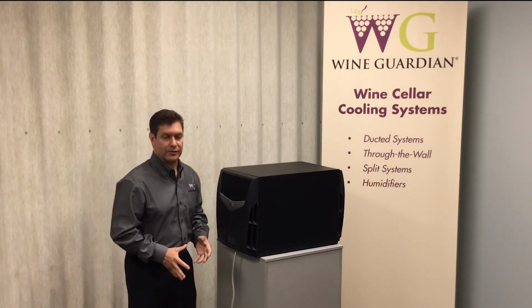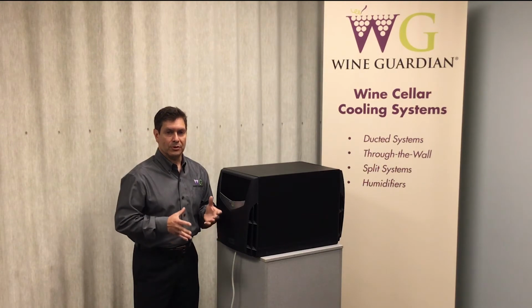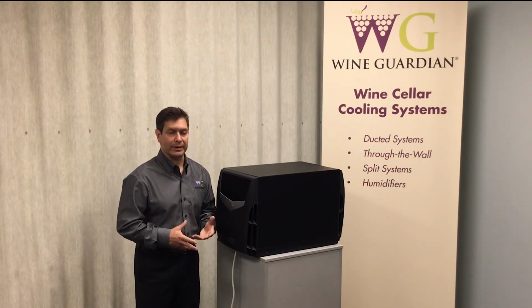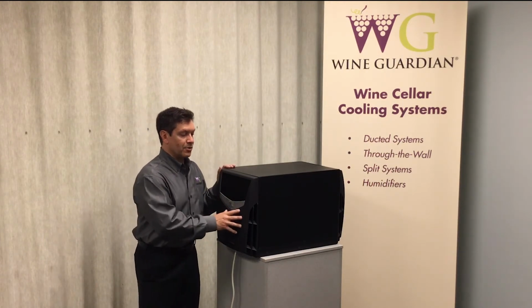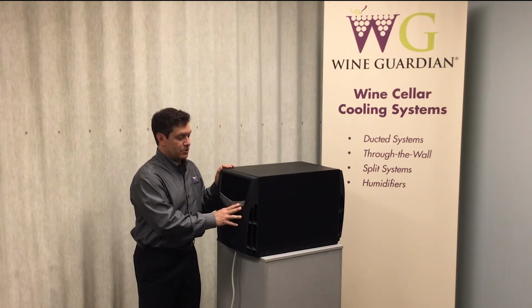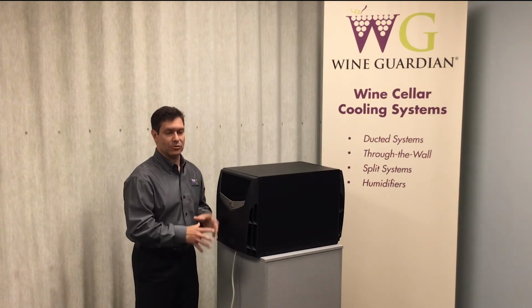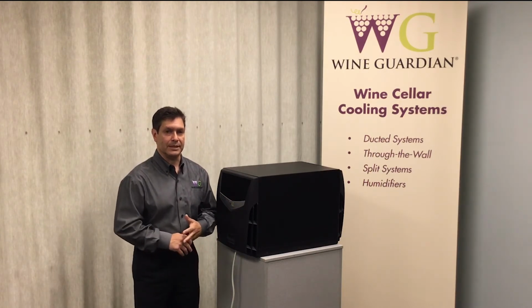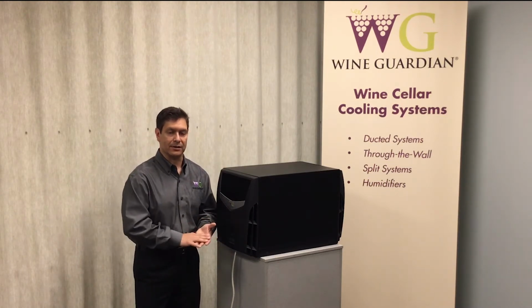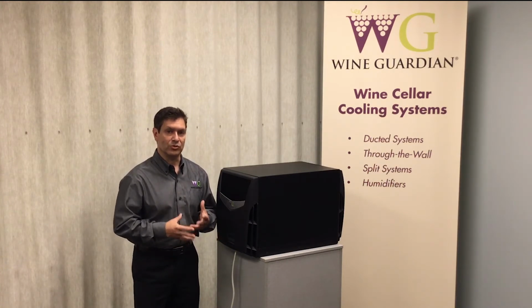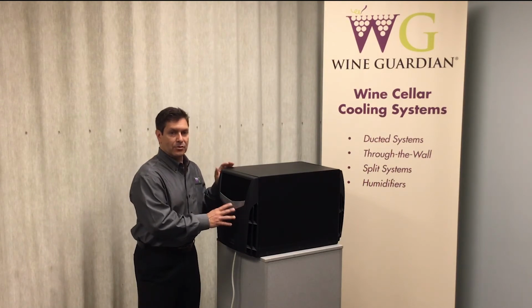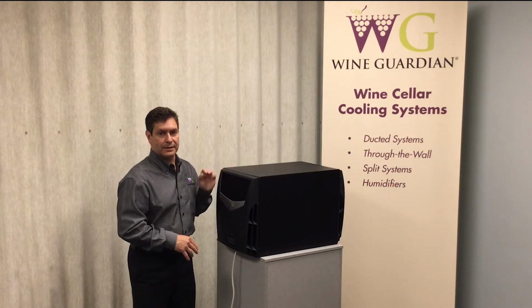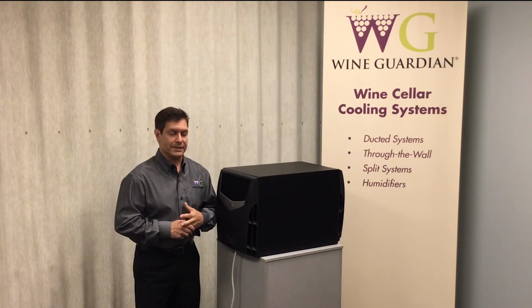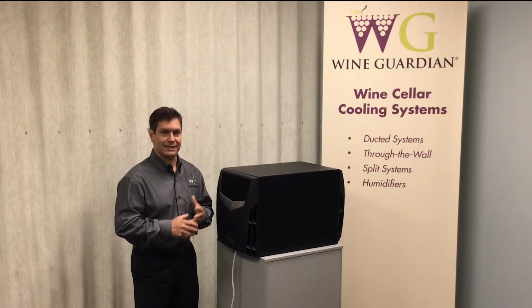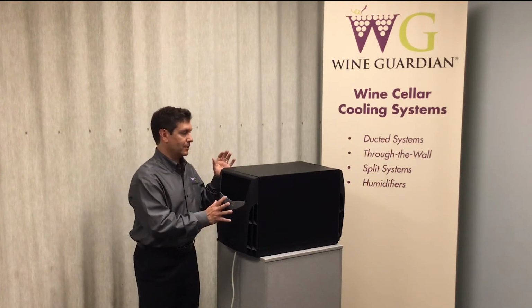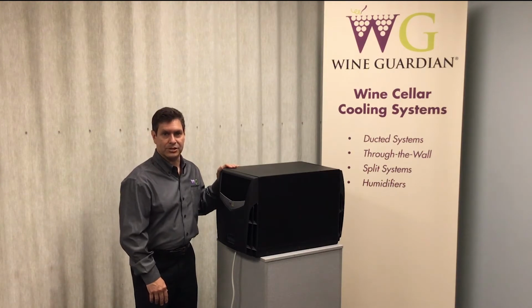Through the wall units, as with all of our wine cellar cooling units, it's important to determine the size of the unit by performing a heat load calculation. Of all of the systems, through the wall units are the ones where people tend to use the cubic foot method to determine the size of the correct unit for the space. It can get you into trouble because all wine rooms are created differently. Some have more glass than others, some have more insulation than others, some are commercial space. You really need to do a heat load calculation to determine the correct through the wall cooling system that is required for the space. We've seen many applications where the unit is just not keeping up with the heat load of the space because they sized it incorrectly. So please do a heat load calculation when determining not only through the walls but all of our cooling unit applications.